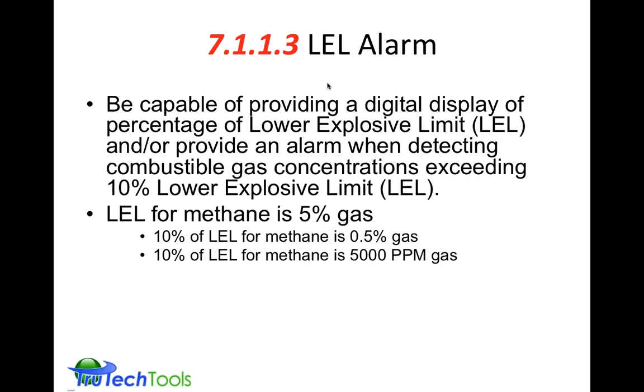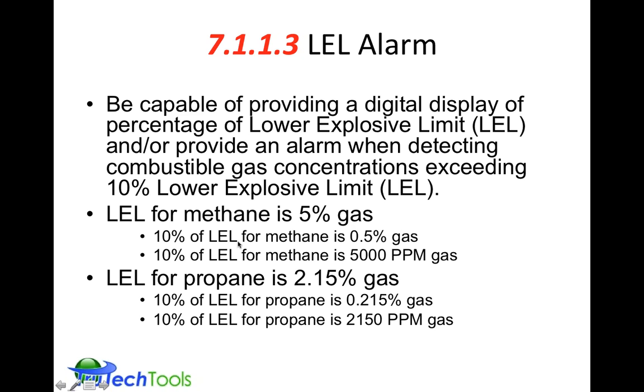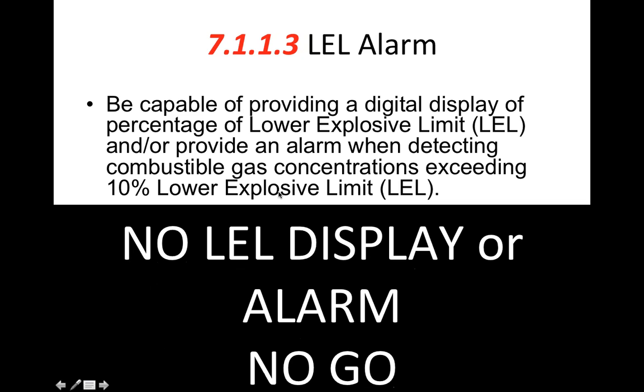The LEL, or lower explosive limit, for methane is 5% gas, which is 5,000 parts per million. And for propane, it's 2.15% gas, which is 21,500 parts per million gas. So there's a measurement here, and if you're familiar with combustion analyzers or CO meters, you're starting to hear some of the similar terminology about ppm. But the explosive limit we'll talk about in just a minute. The basic thing to take away here: if you do not have an LEL display or an alarm at 10% LEL, it's a no-go for your combustible gas detector. It cannot be used and be compliant with BPI 1200.